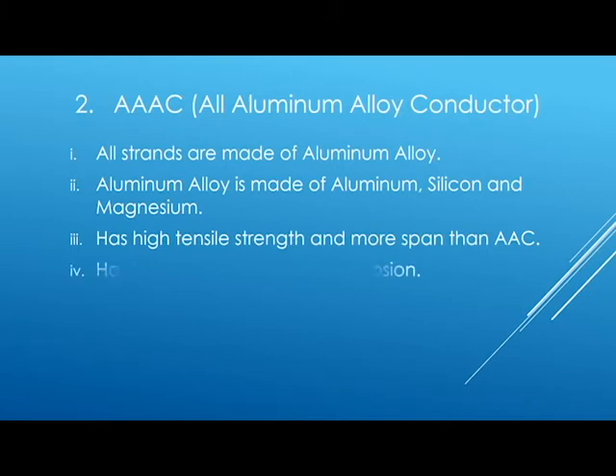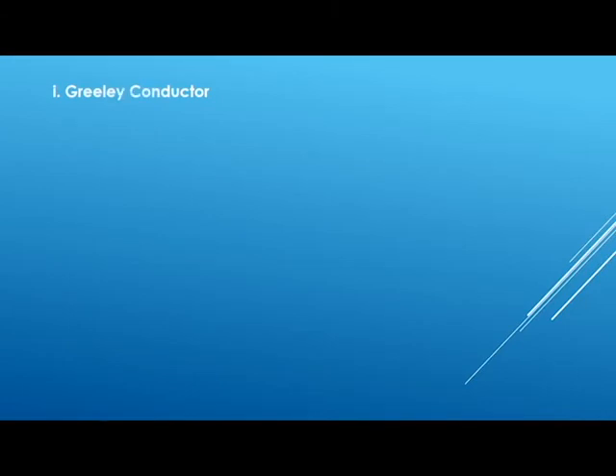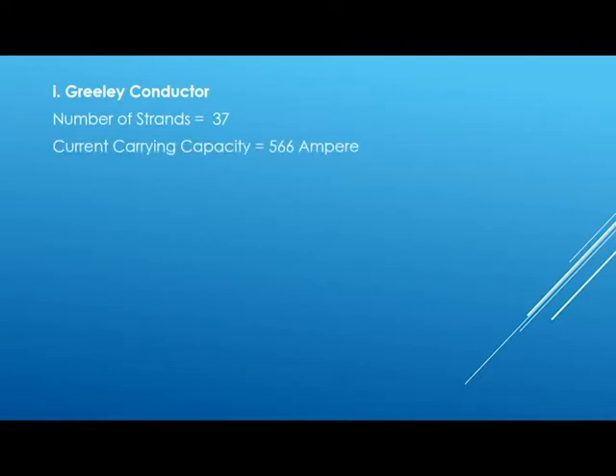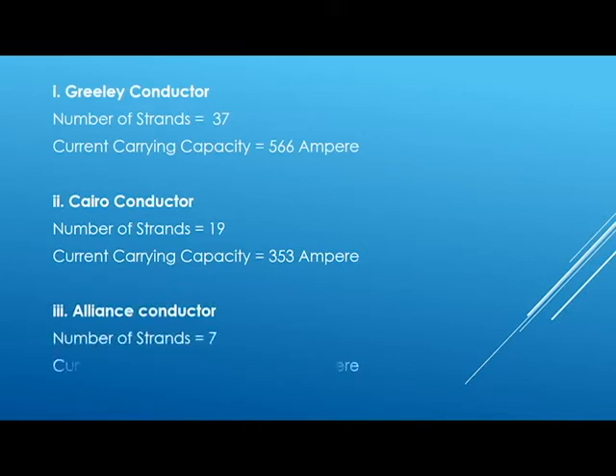AAAC also has high resistance against corrosion. Examples of AAAC conductors are Greeley, Cairo, and Alliance. Greeley conductor is mostly used for 500 kV transmission lines — the number of strands is 37 and its current carrying capacity is 566 amperes. Cairo conductor has 19 strands and a current carrying capacity of 353 amperes. Alliance conductor has 7 strands and a current carrying capacity of 227 amperes.